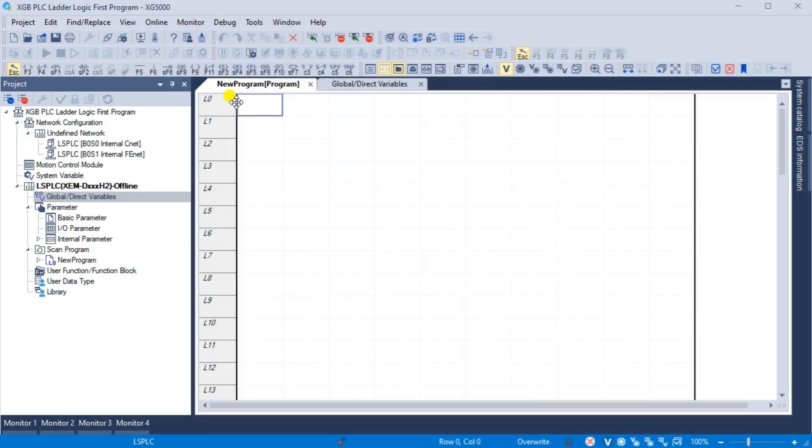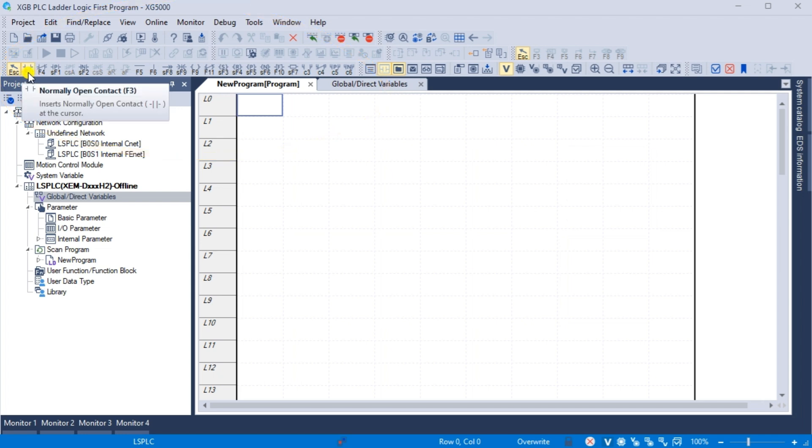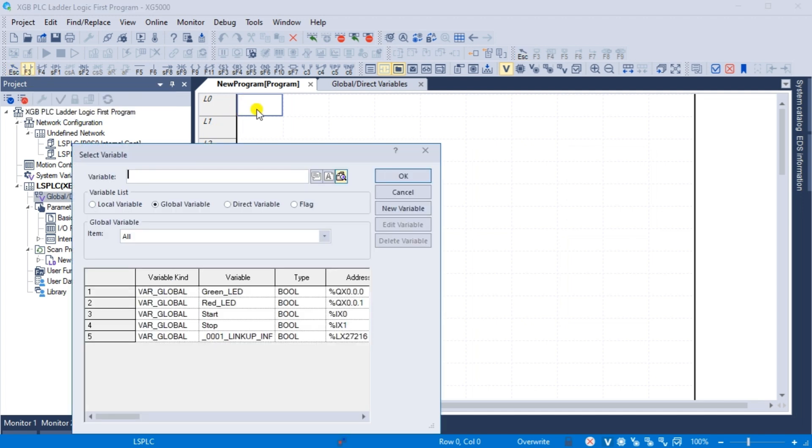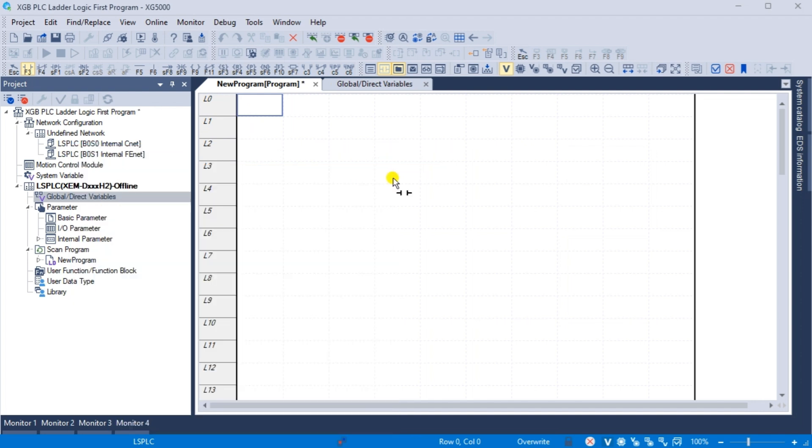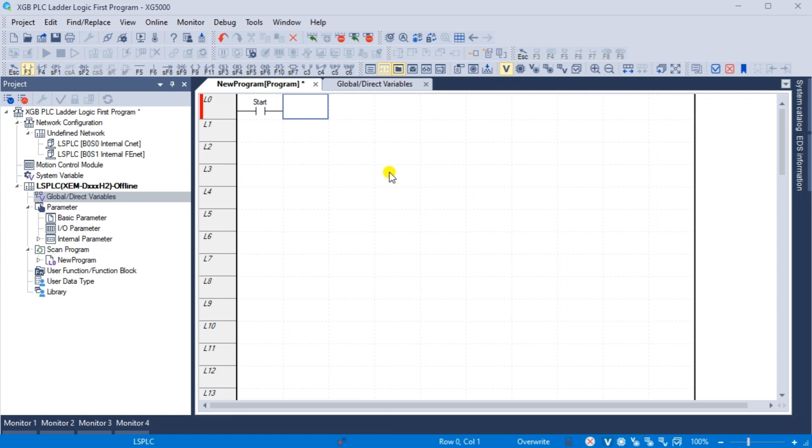Create the ladder logic diagram program. Return to our ladder logic diagram programming window. You will notice all the ladder logic diagram icons for us to use in our program. Select the F3 normally open contact. Click on the workspace where you want this contact to be located. The select variable window will now be displayed. Select the start variable, which we just named, and select OK. This contact will now show on our workspace.